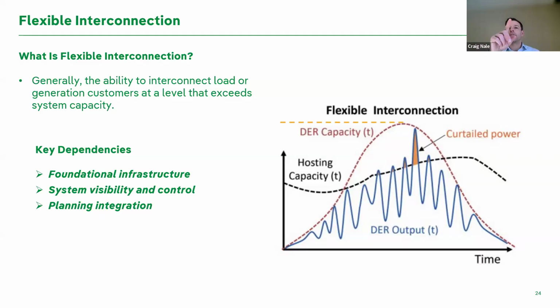It's looking at the capacity of the system, so that black line is the hosting capacity line, and you can see the DER output exceeds that black line in a few places. Without flexible interconnection, we would either need to fully take the DER offline, or we would need to build the system so it met that peak of the blue line.